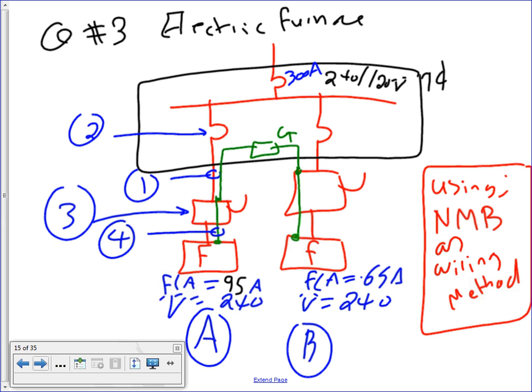And the code, for the most part, I would say everything that we do, 70% is the same. Do you guys see the redundancy? What differs is, do you multiply by 1.5 one time, or 1.25 one time, or 1.75 one time? And that's the knowledge that you have to have. And if you get confused, write yourself a note. If I do a motor with a circuit breaker, I multiply by 2.5. If I do an appliance, I multiply by 1.5. Okay, shall I move on? Yes?